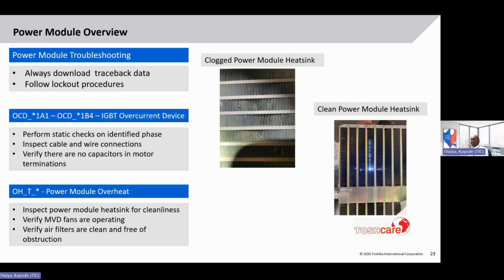One of the things you can do if you have doubts about your heatsink is you can shine a light through it as shown on the right, making sure that that light is visible at the top. So if the heatsink is clean and free of obstructions, you should see the light come through properly. Next thing is to make sure the fans on the MVD are properly operating. And I mentioned that the transformer provides power to those fans. So if they are not operating, or if they are operating backwards, that can cause a power module overheat because power devices need proper airflow. And finally, the air filters that I mentioned also need to be cleaned. Any obstruction to those can also cause a power module overheat.